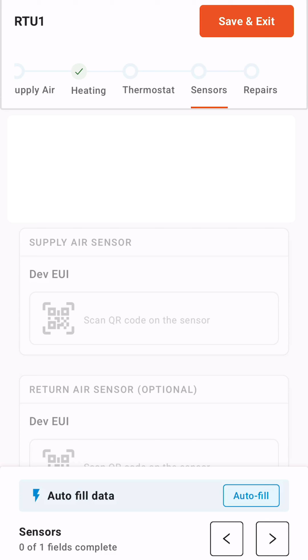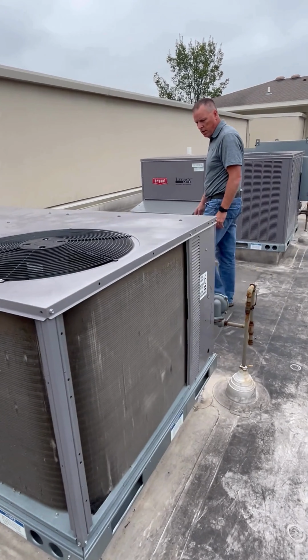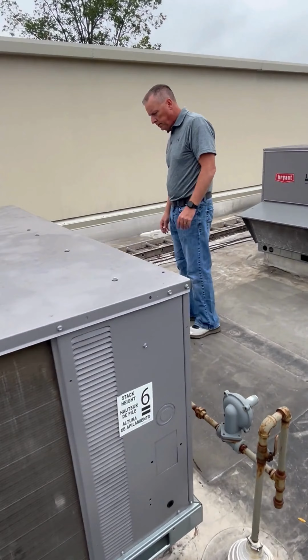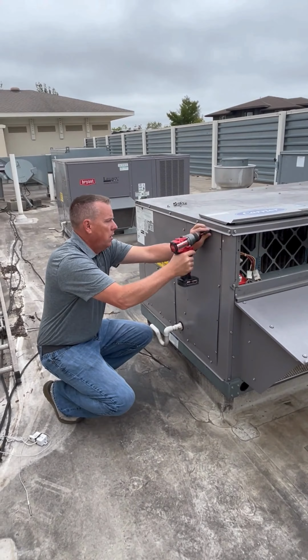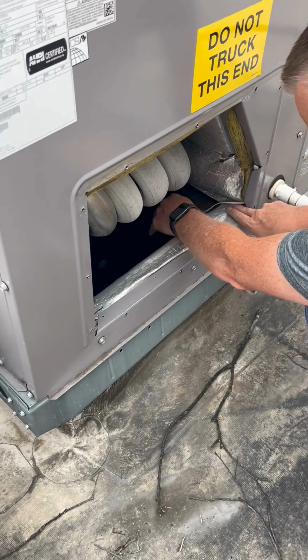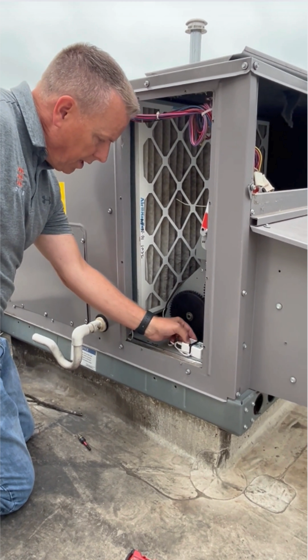Before doing anything on the sensors step, you'll need to install the Monaire supply sensor and then the return sensor. First, you should determine where the supply and return areas are within the unit. You'll remove the panel and mount the supply sensor as far away from the heat exchanger as possible. In this example, we're actually able to mount the supply sensor in the unit's return area and feed the probe into the supply area. If this is possible, this is preferred because it ensures the sensor won't be affected by the heat generated from the heat exchanger.